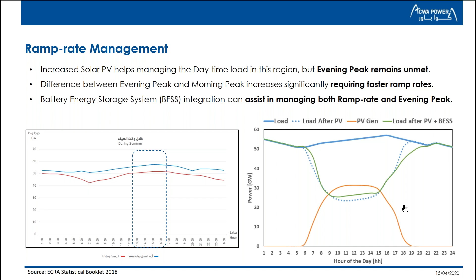Moving on to the next issue, which I mentioned in the previous slide, is mentioned in the next slide, which is the variability of PV. Now, PV inherently is variable in nature. In the shorter time scale, it has infirm behavior. Now, the ability of a grid to handle such infirmness depends on the type of loads that are connected, on the non-PV generation assets that are connected, and on the grid strength in itself. But as the proportion of PV increases, the inertia of the grid reduces, and hence its capability to handle such infirmness reduces.